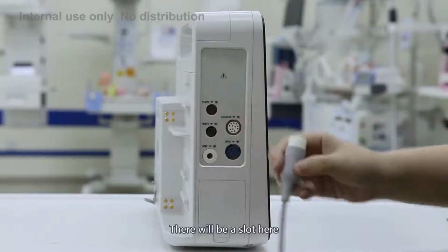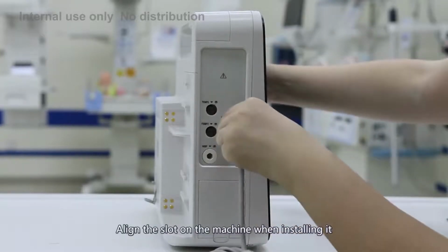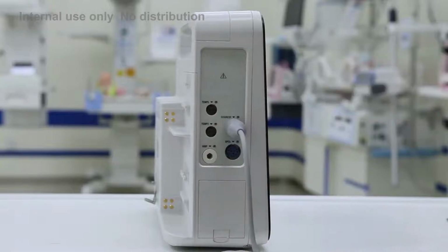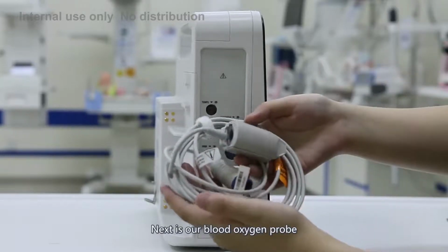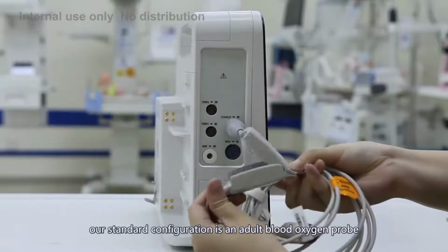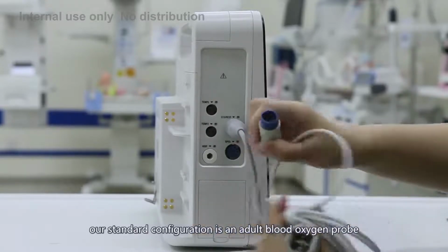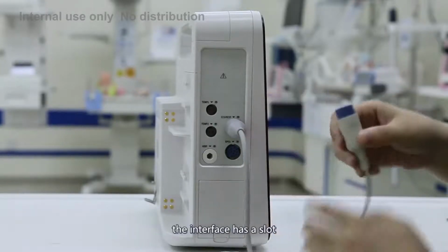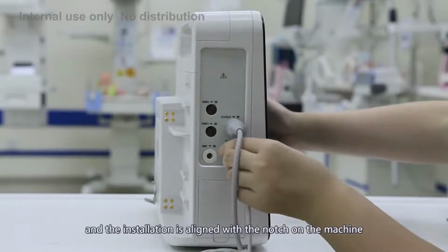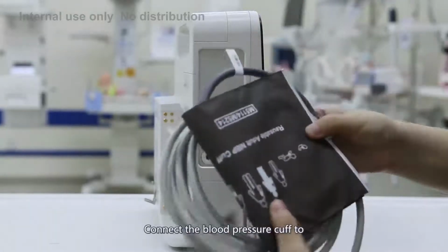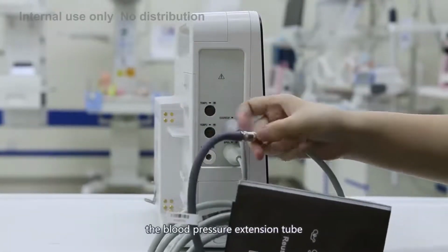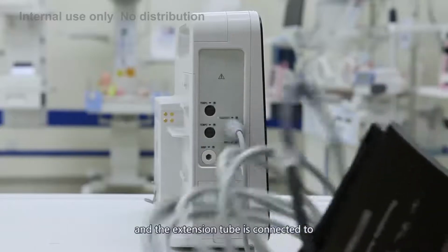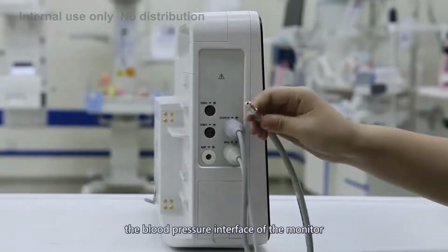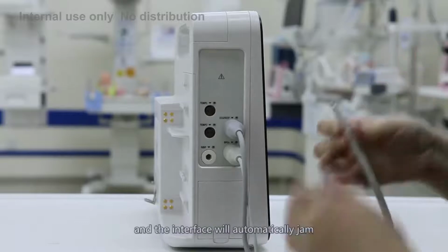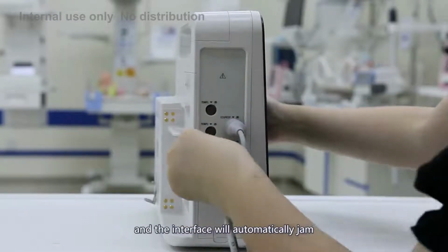There will be a slot here. Align the slot on the machine when installing it. Next is our blood oxygen probe. Our standard configuration is an adult blood oxygen probe. The interface has a slot, and the installation is aligned with the notch on the machine. The last one is our blood pressure cuff. Connect the blood pressure cuff to the blood pressure extension tube, and the extension tube is connected to the blood pressure interface of the monitor, and the interface will automatically lock.